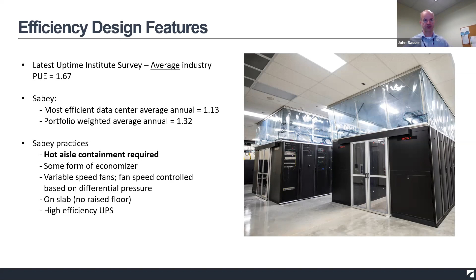And of course, we use high efficiency UPS. The UPSs about 10 to 15 years ago started becoming much more efficient than the ones before. It wasn't uncommon in 2000 to have 10% plus losses on your UPS. Now it's very common to have 3% or less losses on the UPS modules. Next slide, please.